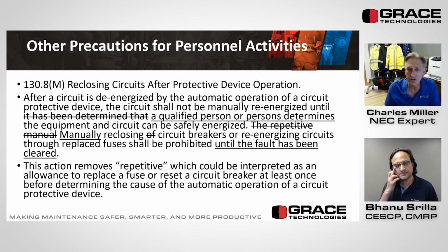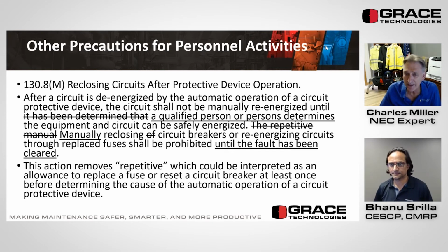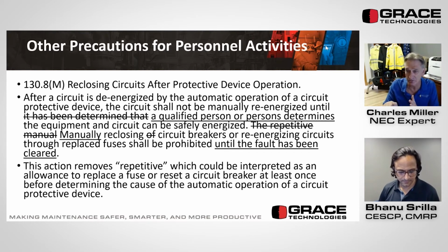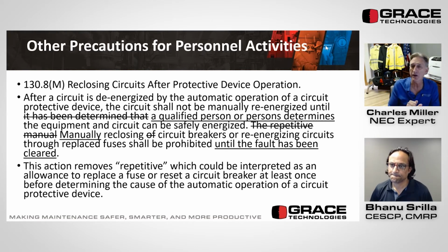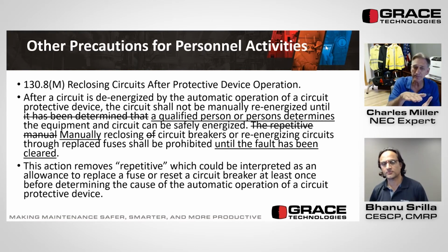After a circuit is de-energized by the automatic operation of a circuit protection device, the circuit shall not be manually re-energized until a qualified person or persons determines the equipment and circuit can be safely energized. Now, the word repetitive is gone. Manual reclosing of circuit breakers or re-energizing circuits through replaced fuses shall be prohibited until the fault has been cleared.